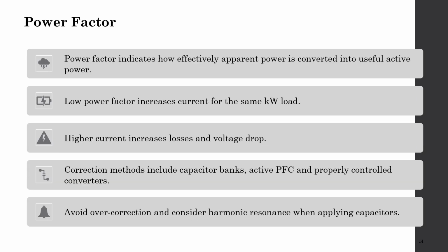Power factor. Power factor indicates how efficiently apparent power is converted into useful active power. Low power factor increases current for the same kilowatt load. Higher current increases losses and voltage drop. Correction methods include capacitor banks, active PFC, and properly controlled converters. Avoid overcorrection and consider harmonic resonance when applying capacitors.